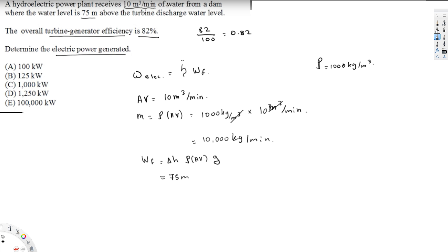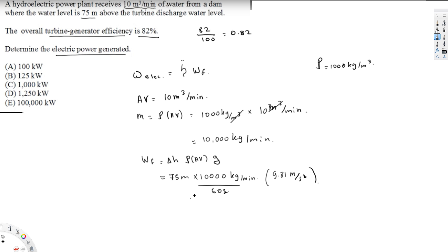We have all the information: ΔH = 75 m, and the mass flow rate is 10,000 kg/min. We must convert to per second by dividing by 60 seconds. Then multiply by g = 9.81 m/s². Calculating this gives the maximum power that could be generated by the fluid stream, which comes out to 122,625 watts.